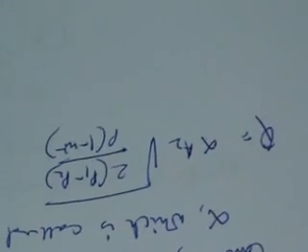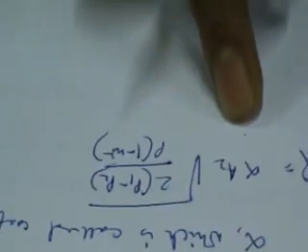For this purpose, we can do the experiment and measure the delta P across the orifice plate, and taking the dimensions of the orifice plate, the area ratio and density, all those things, we can find out A2 root over (P1 minus P2) by rho times (1 minus m square).